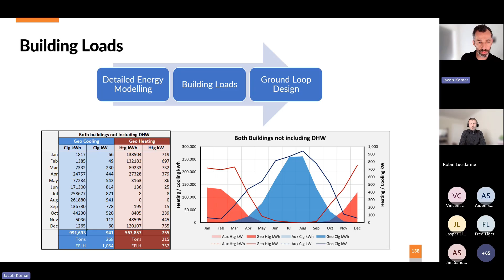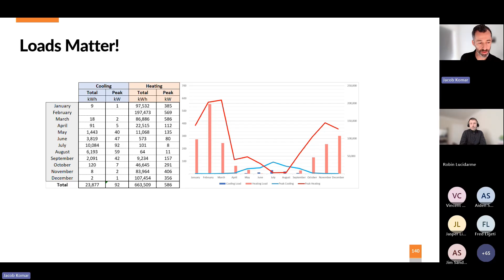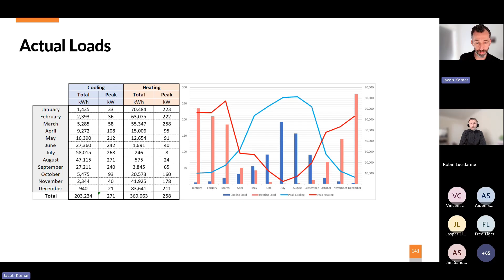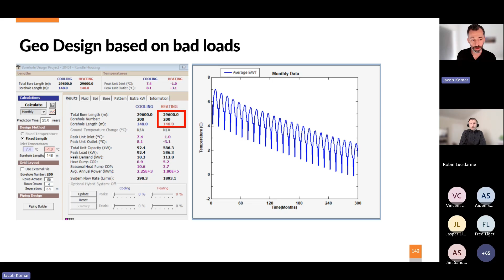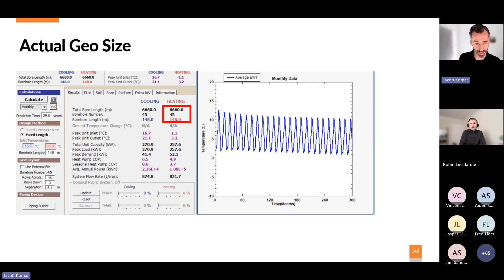Our client sent us these loads saying, hey, we don't want to pay you for energy modeling. Can you just run with our loads? Their loads were 663,000 in heating and 23,000 in cooling. The numbers weren't making sense to us when we ran it, so we reran the model. Our heating loads were half of that, and our cooling loads were 10 times that. Compliance models are not realistic energy models. Loads matter. With their design, we would have needed 200 boreholes, and you can see how the ground's going to freeze over time. With our design, we only need 45, and the Earth's temperature is stable. Unfortunately, it does take more careful design. That's the reality.